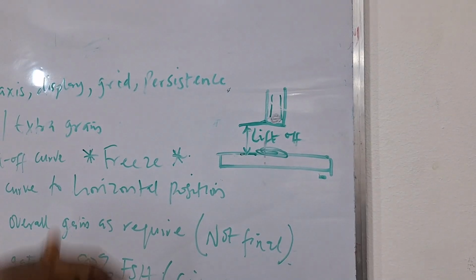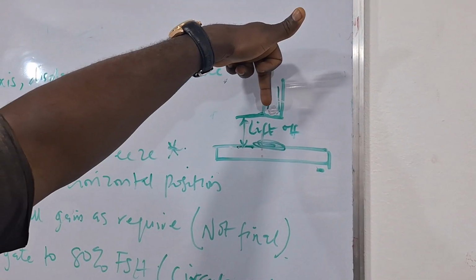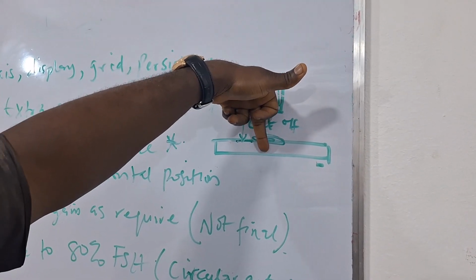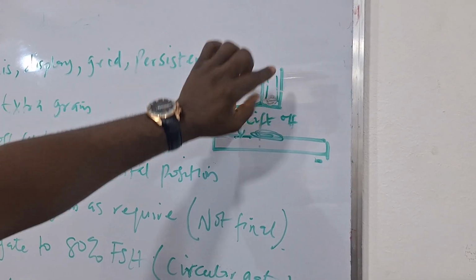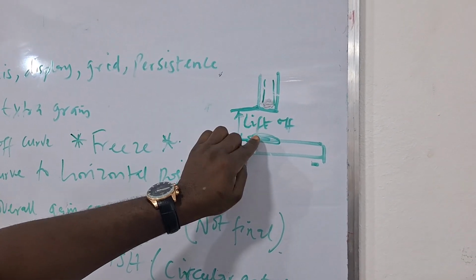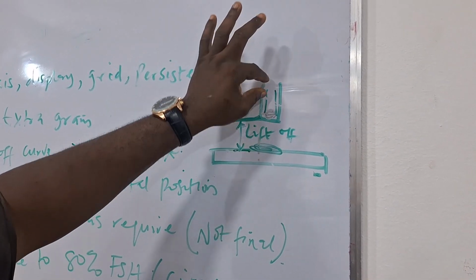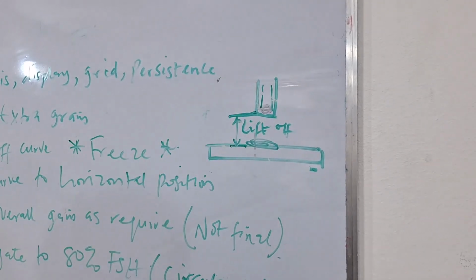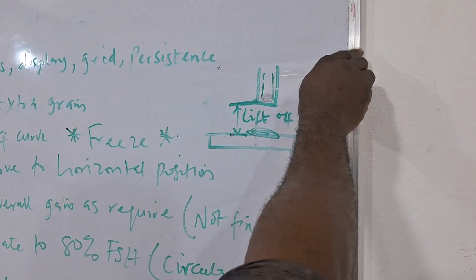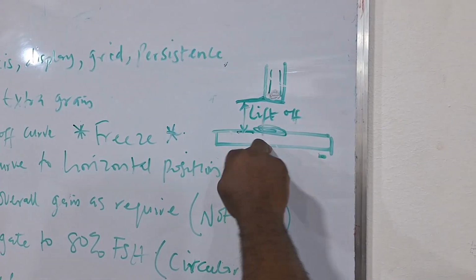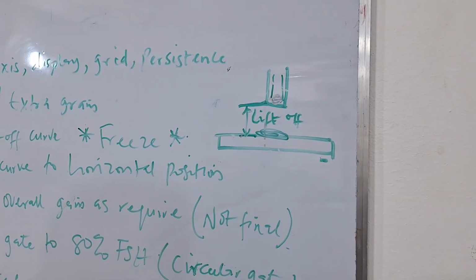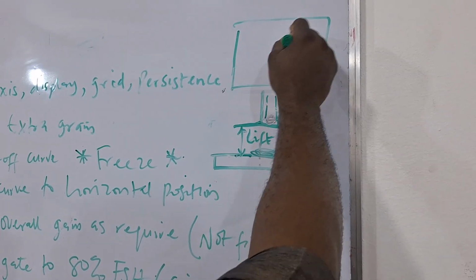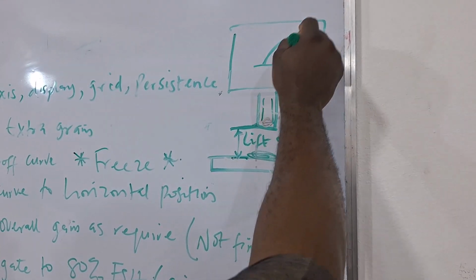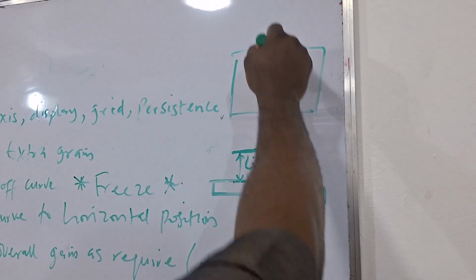So what happens is this probe has magnetism and is coming to the plate to produce eddy current, and the eddy current is producing opposing magnetism, which will affect the voltage of this coil, thereby leading to an increase in impedance. By virtue of bringing this probe to this plate, impedance has increased, and that increase in impedance, if this is your lift-off plate, is going to show as a curve. This curve is what we call the lift-off curve.